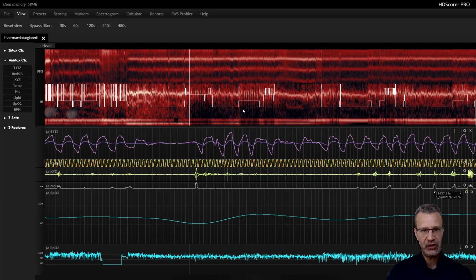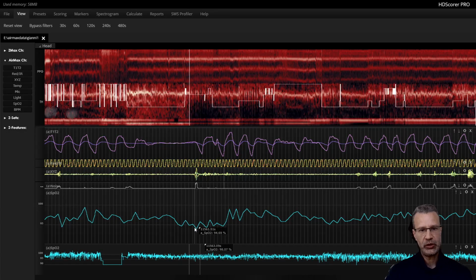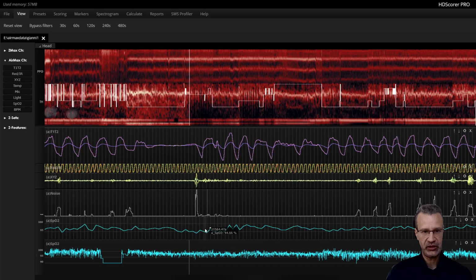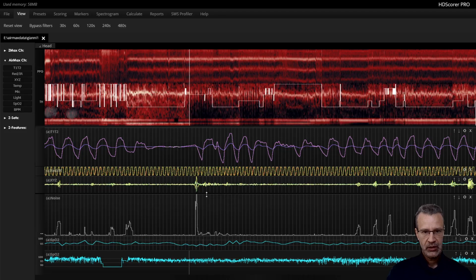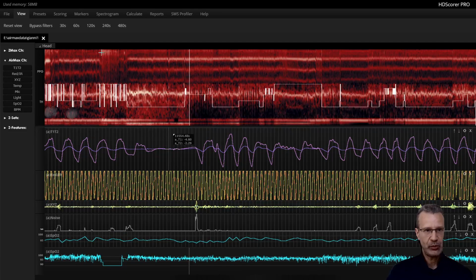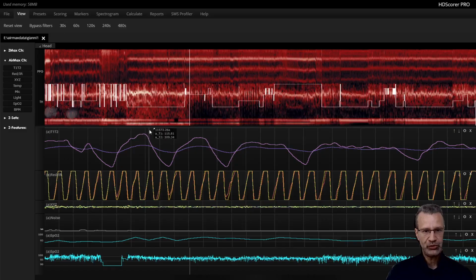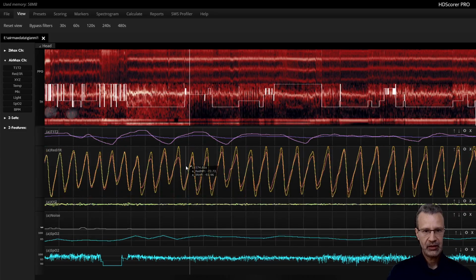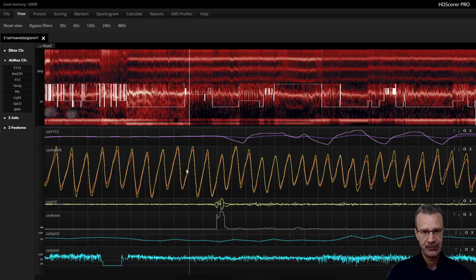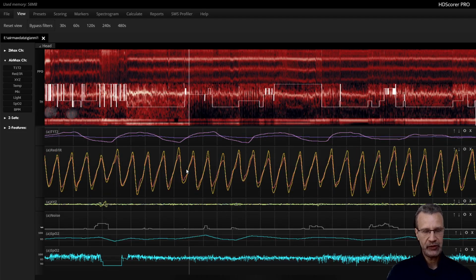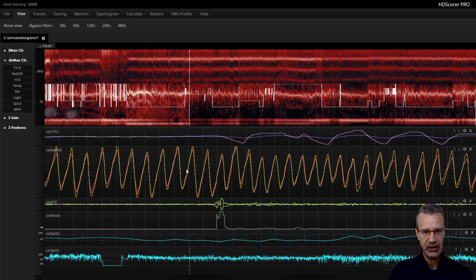So the benefit of having a very good algorithm is that it doesn't get confused. And so when you're looking at these little spikes, this is real data. It's not noisy because the calculation is noisy intrinsically. It's noisy because that's the actual value that got computed. This is a little bit of a pro tip. When you want to validate and you see a big gap between two consecutive readings and you ask yourself, is this real? So a little bit of an inside story on how you calculate the SpO2.